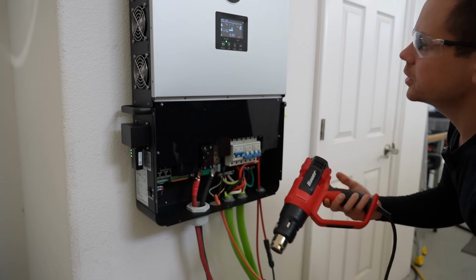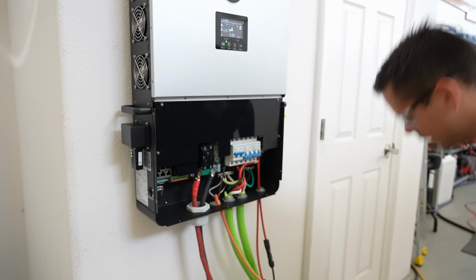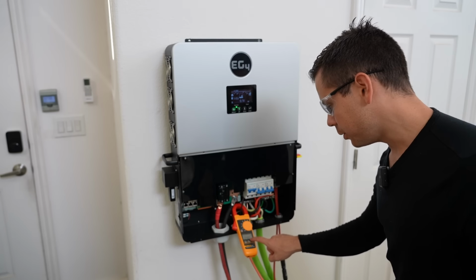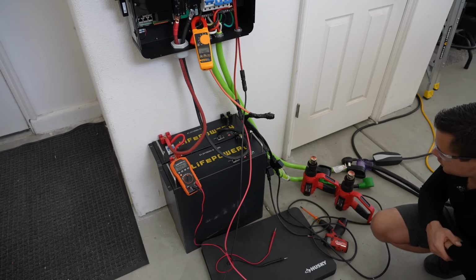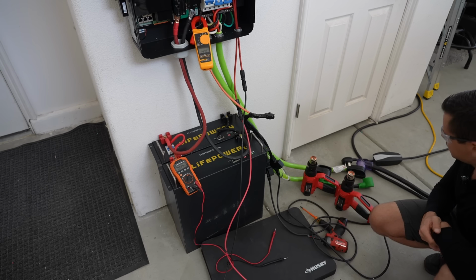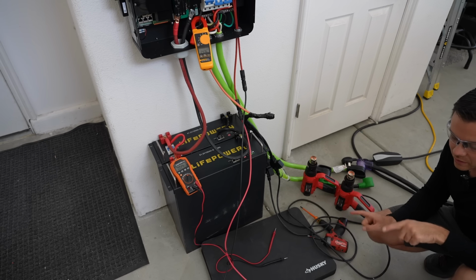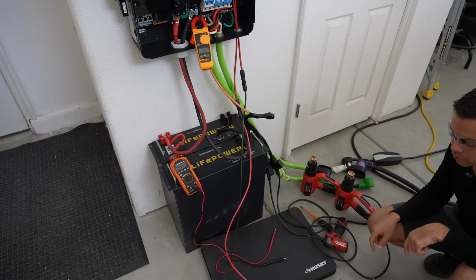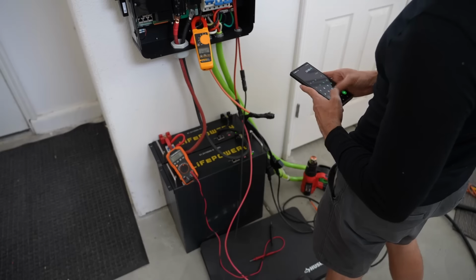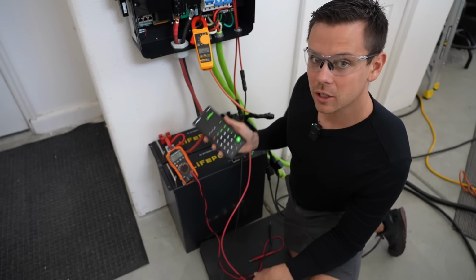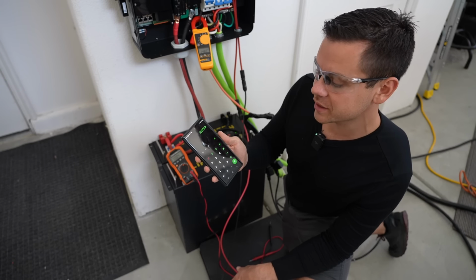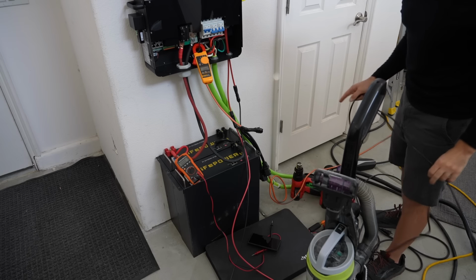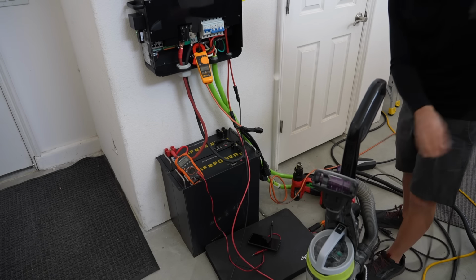And heat gun number 2, 3.1 kilowatts. That's 24.8 amps. So we're gonna run this for a few minutes and see if it trips. This does not have line balancing like the 18K. It only does 3,000 watts continuous. And with my meters, it says 2,979 watts. We could do a heat gun in a vacuum and see if it can handle that.